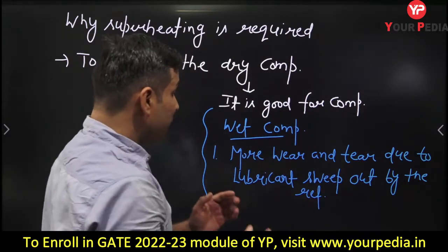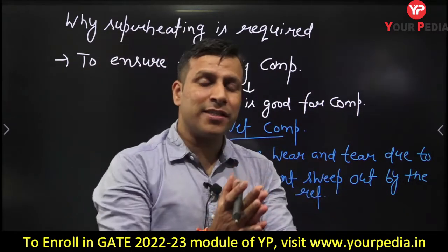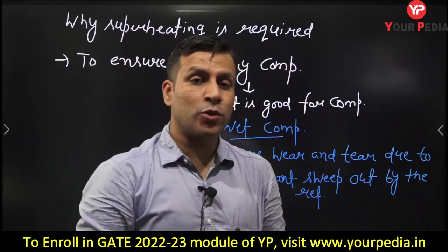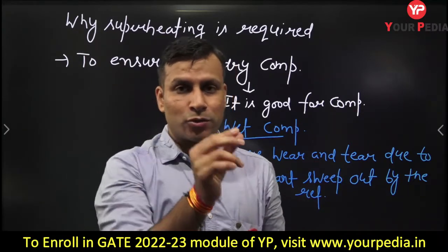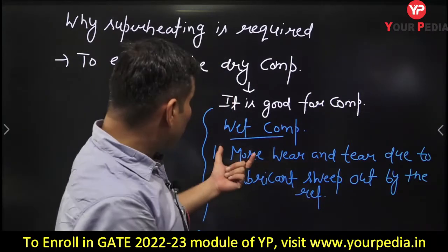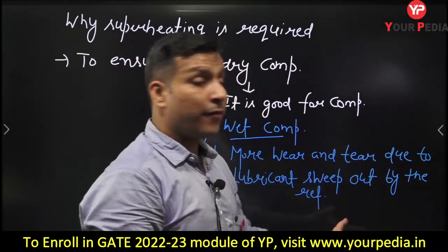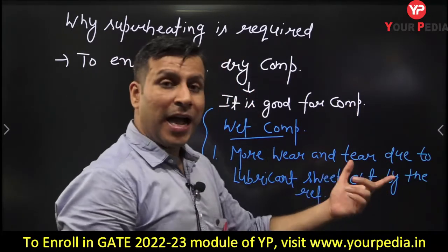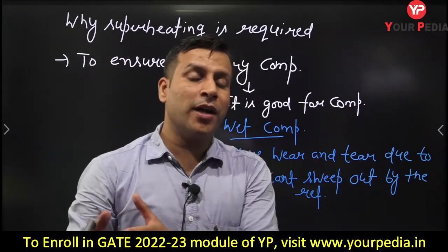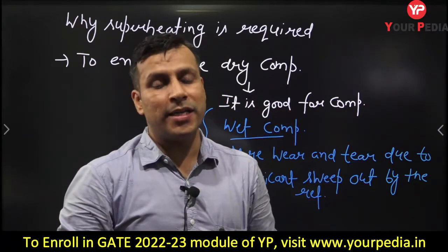When the wet refrigerant is entering, it has some liquid refrigerant in it. There are vapor particles and also liquid particles. Those liquid particles sweep out the lubricant, and due to that there will be more wear and tear in wet compression.